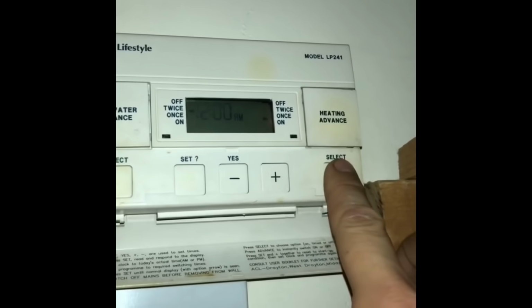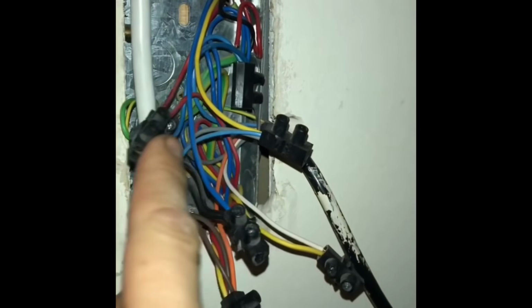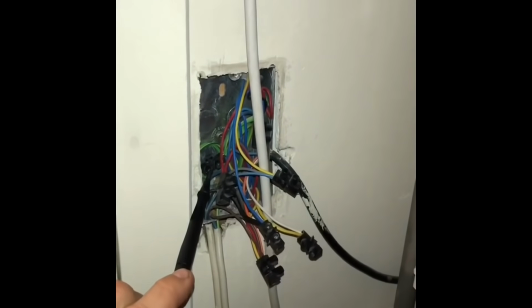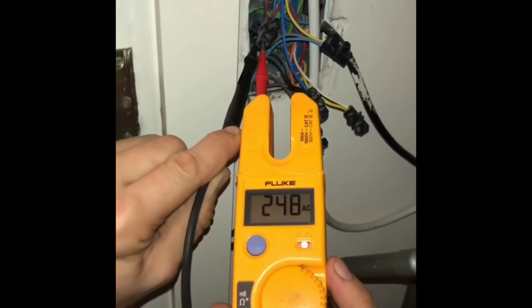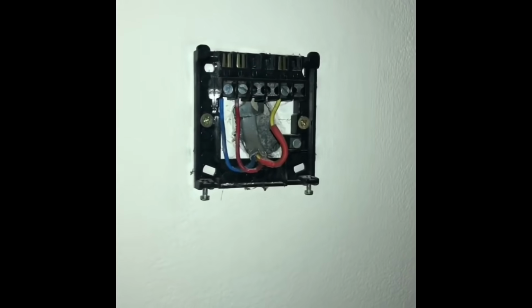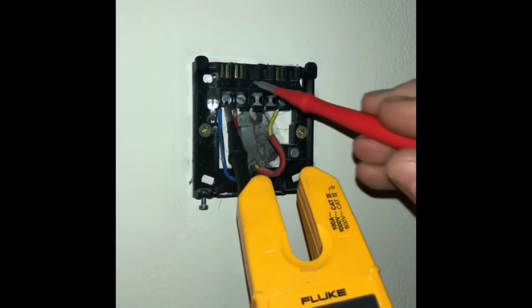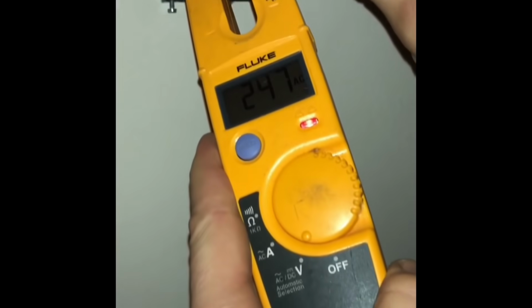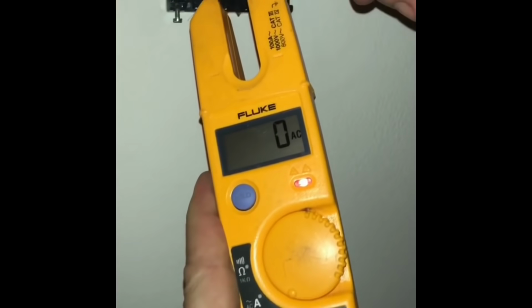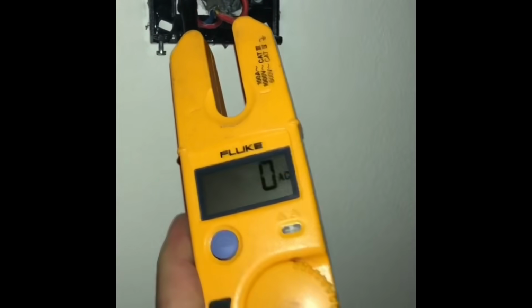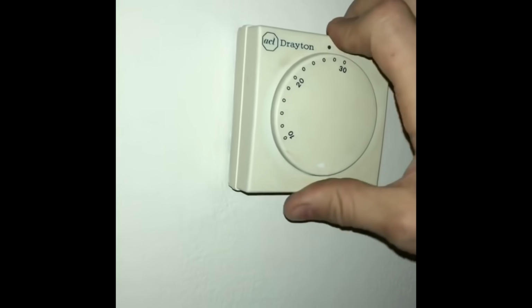I've already had this off the wall, and I know that the red cable is the switch line for the central heating. So when I call for a demand, I should have 240 volts on this red cable. If I've not, then I know the programmer's at fault. Because I have, then I go to the next step in the series, which is the room thermostat. We've got 240 volts down to the room thermostat. So the next thing we need to check is that we've got 240 volts going back up when the room stat's calling on the yellow cable.